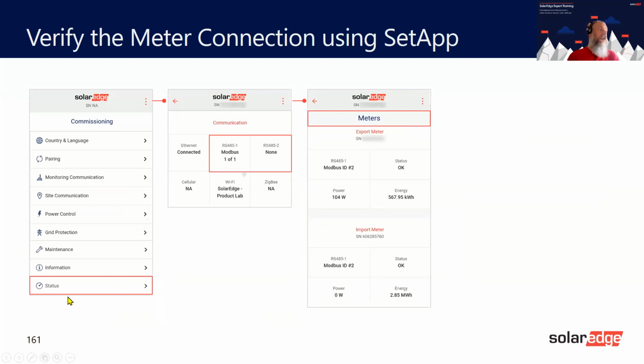Once you've done that, you can then check in the status screen, which again is in the commissioning screen here. So go to status. You can see on here RS485-1 Modbus 1 of 1. That tells you you've got 1 meter connected or one device connected. You can see you've got nothing or none in RS485-2. And then if we look at this one here, we can see RS485-1 Modbus ID 2, which is what we set it to. It says OK. It's telling us what the power is, what the energy is, the import meter. So that was the export meter, the import meter. We've got ID2, OK, and so on. So this allows you in the status screen to see, and these values will change. If you're standing in front of the inverter and the inverter is producing, or the property is demanding stuff from the grid, these values will change. So you'll be able to see it working in real time. It will be real time.